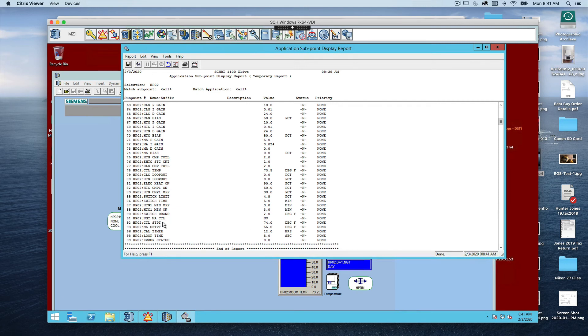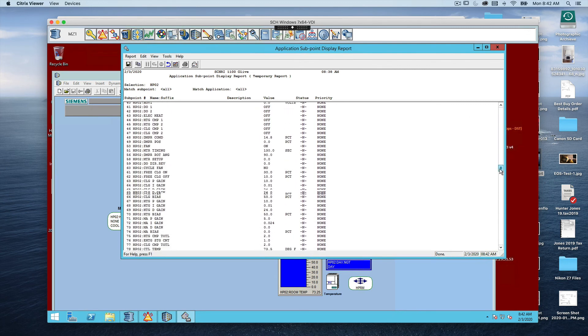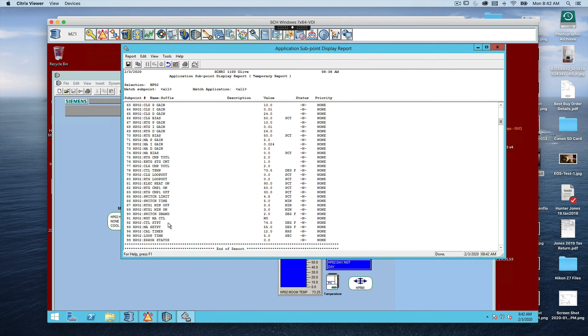If we were going to change the temperature in the room, we could either change the control set point to make it higher or lower, or we could change the heating and cooling set points to different values — raising the cooling set point to start cooling at a higher temperature, or lowering the heating set point to turn on heat at a lower temperature. What we'll do right now is change the control set point from 74 degrees down to 73 degrees. To change the set point, you double-click on that particular line to bring up a commander screen.